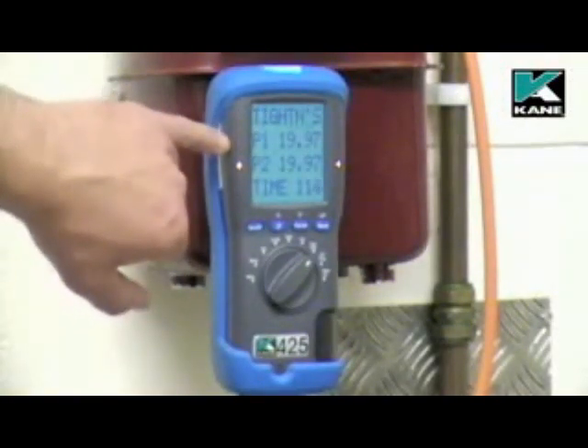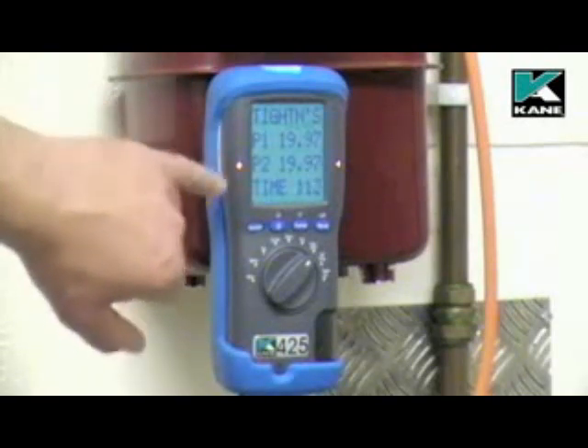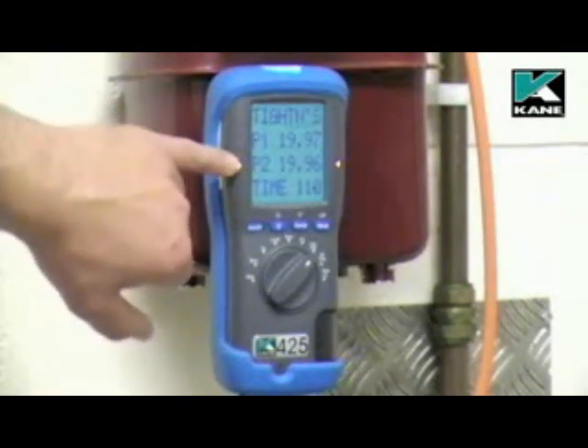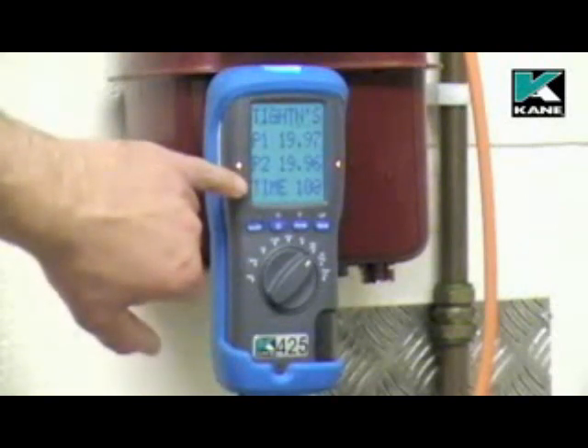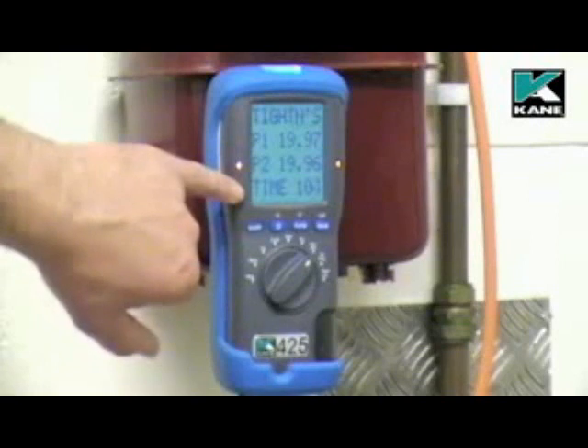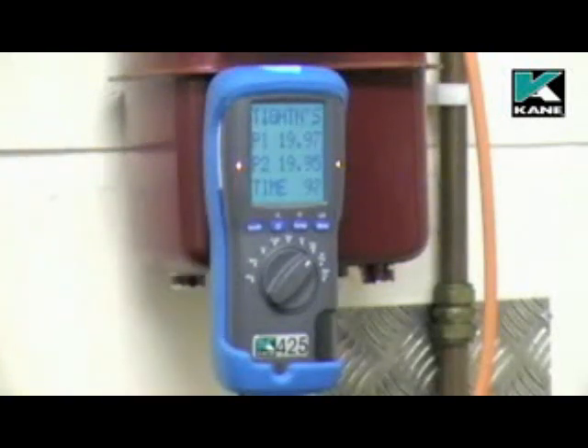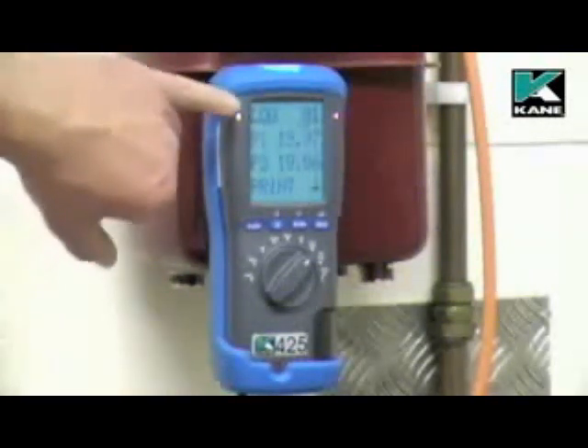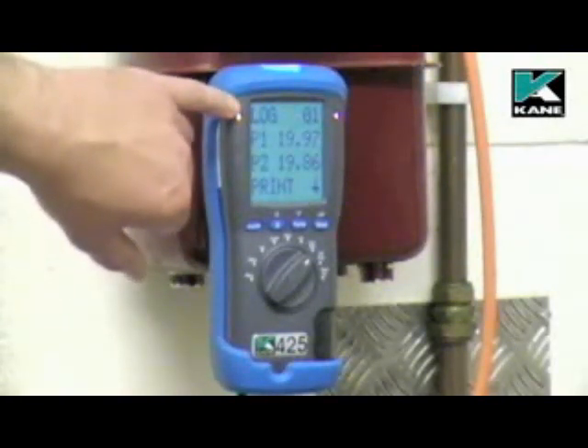P1 is the pressure at the start of the tightness test, P2 is the current pressure, and again there's an internal clock to time the test for 120 seconds. That time can be adjusted via the menu. The tightness test has now been completed. The results have been logged in the memory as test number 1.